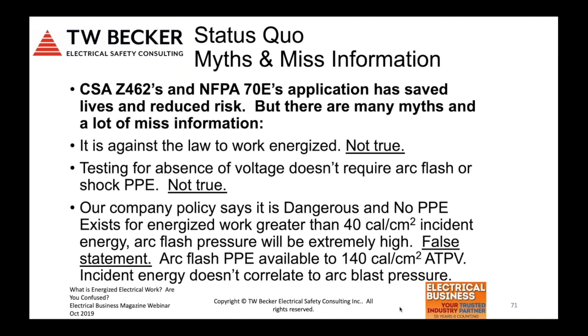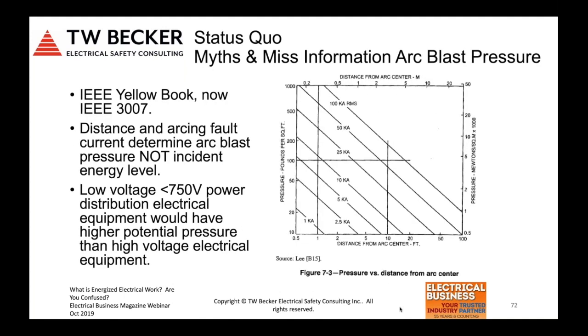The next one is: our company policy says it's dangerous and no PPE exists for energized electrical work greater than 40 calories. Incident energy, arc flash pressure will be extremely high. That's a false statement. One, arc flash PPE is available up to 140 calories ATPV, and the arc blast pressure doesn't correlate to incident energy. So 40 calories is not a dangerous incident energy level. And I would encourage you that when you do your risk assessments and you look at potential injury and damage to health, that you do consider arc flash suits up to 140 calories. So again, I did show this graph about the blast pressure, trying to give evidence that incident energy doesn't correlate to the blast pressure.